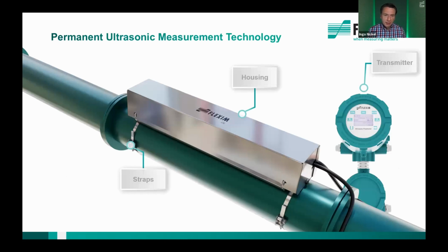Yeah, in this picture you can see clamp-on technology is a very reliable and robust measuring equipment. As you can see, our equipment is fixed very robustly on the pipe. We have special straps. We have a housing for our sensors, and this avoids any contact with rain or other condensed water. And so our sensors are fully secured with this additional housing.